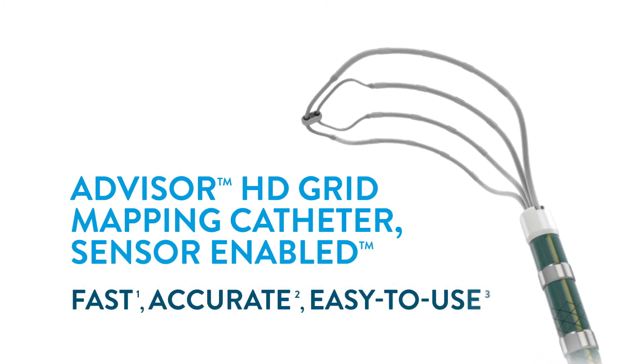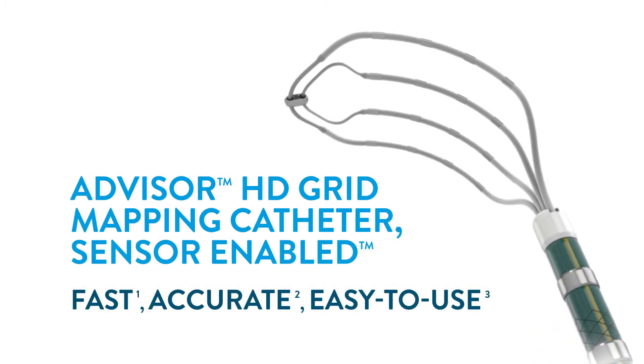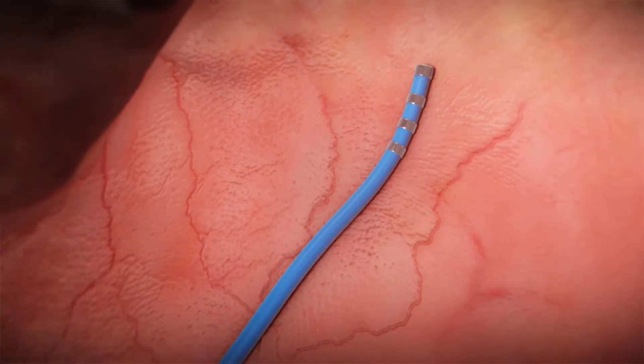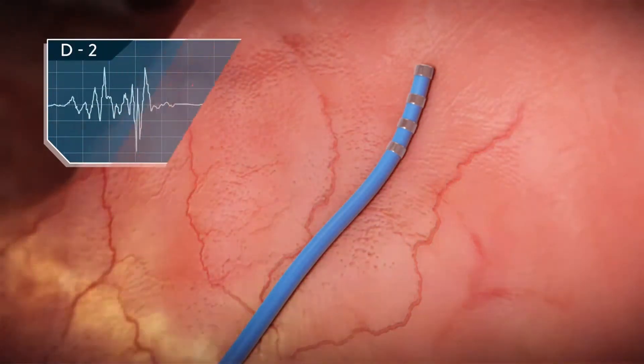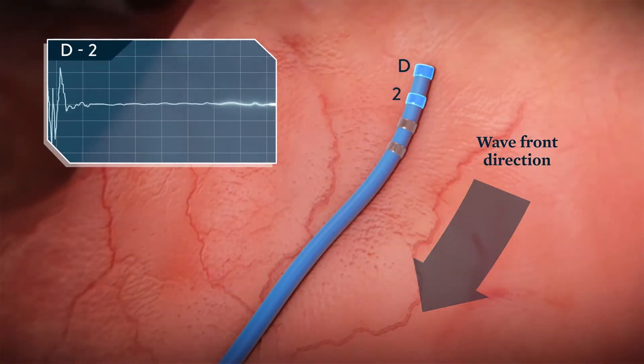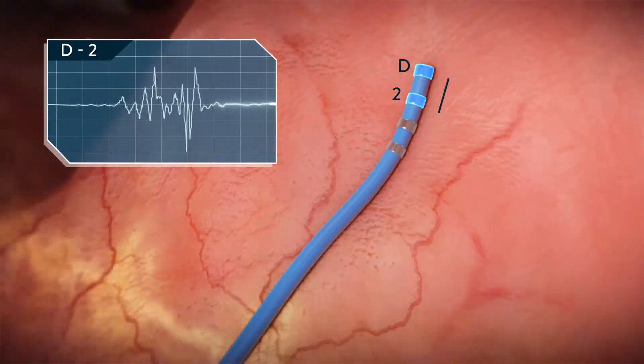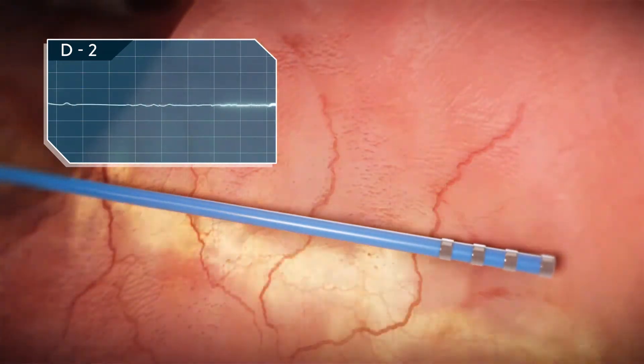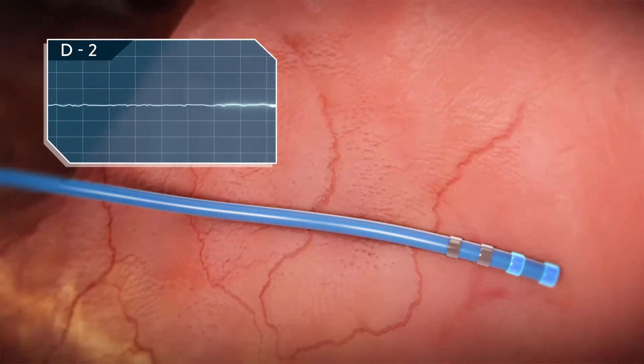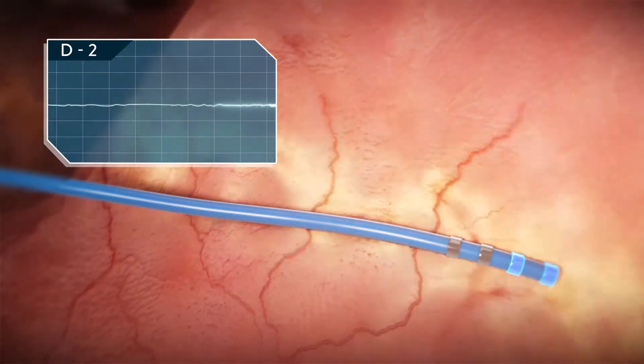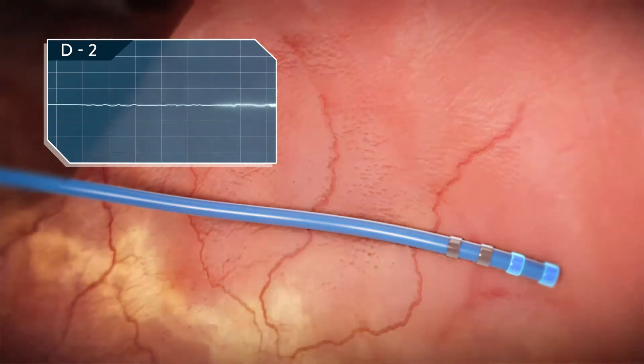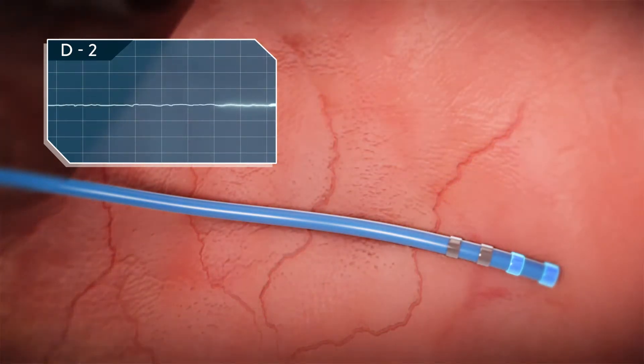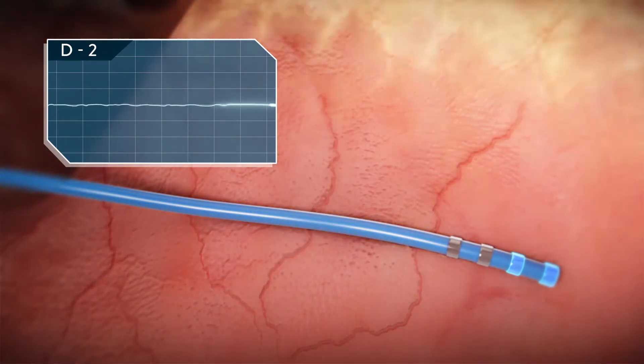When using traditional mapping catheters that only collect data with linear bipoles, the orientation of the catheter relative to the wavefront can make it challenging to correctly assess activation timing and voltage. When the activation wavefront is moving parallel to the electrode pair, the maximum amplitude is recorded. When the wavefront is moving perpendicular to the electrode pair, both electrodes record the voltage at the same time, creating a cancellation — no spike is recorded on the resulting bipolar pair.